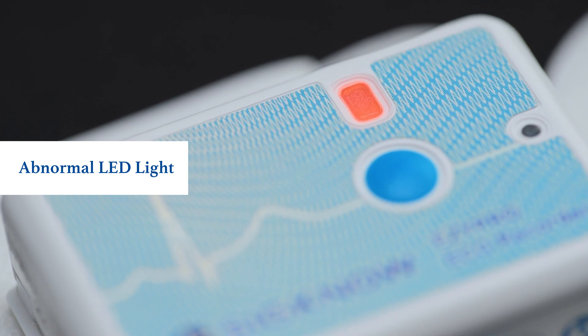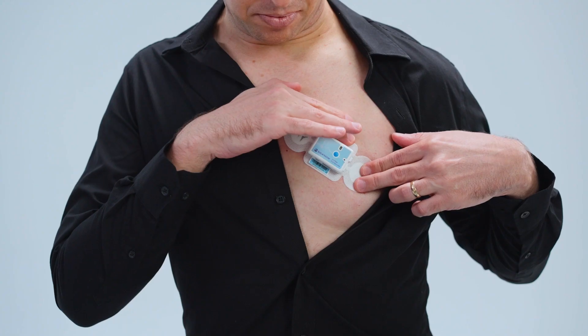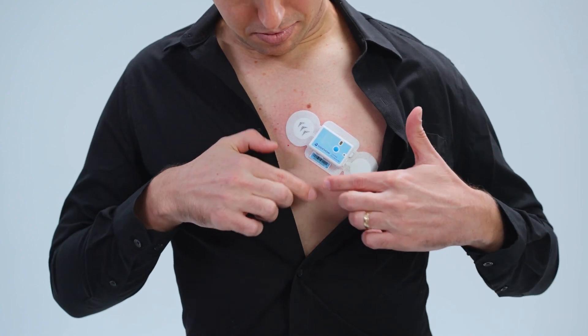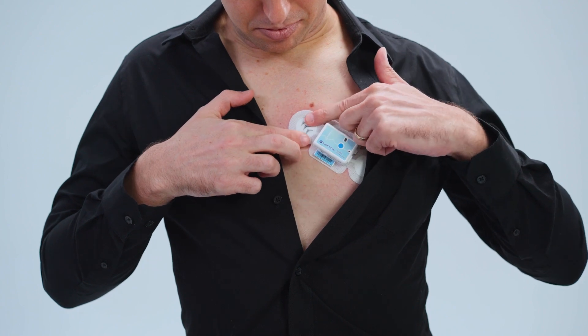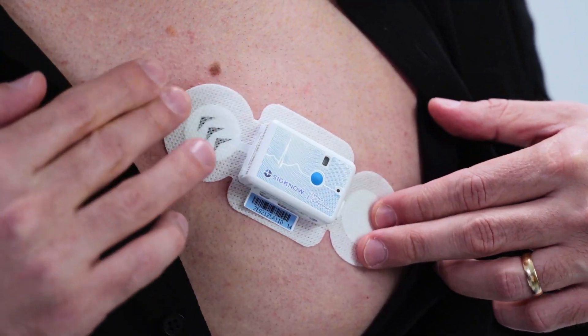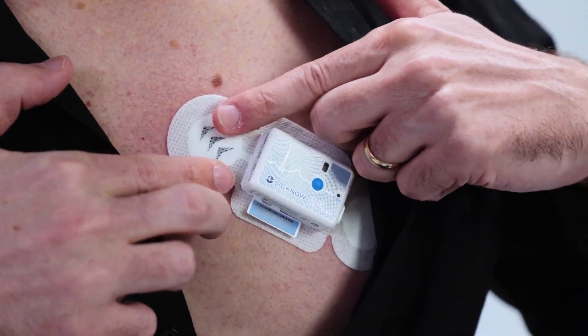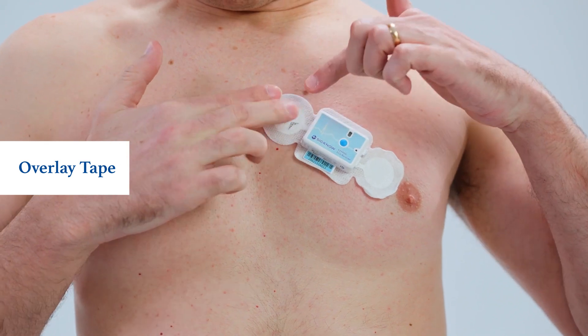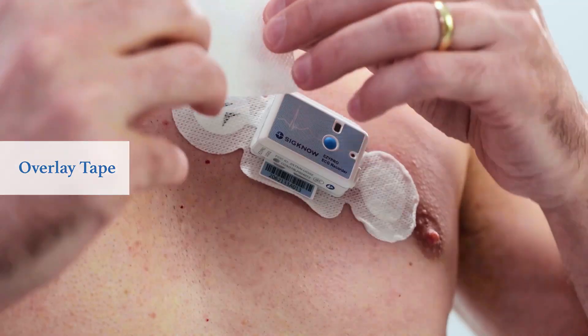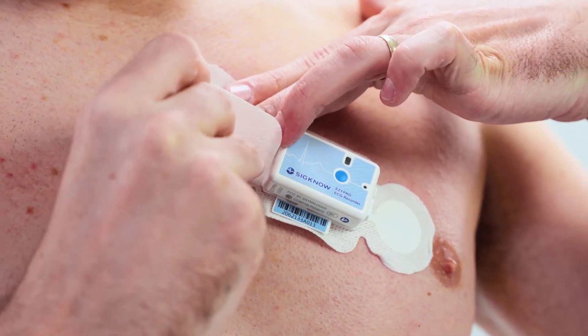There's no light during recording. When the patient sees an orange light flashing, they must press the patch for two minutes to help the patch have better contact to the skin. If the orange light keeps flashing or a red light appears, please ask the patient to call their healthcare provider. When the patient sees the patch starting to peel off at the edges, they can use the overlay tape packed in the box to enhance the adhesion if necessary.